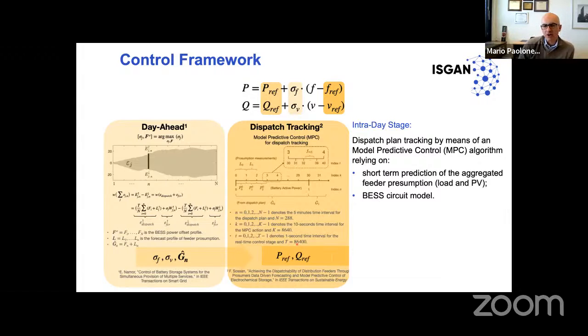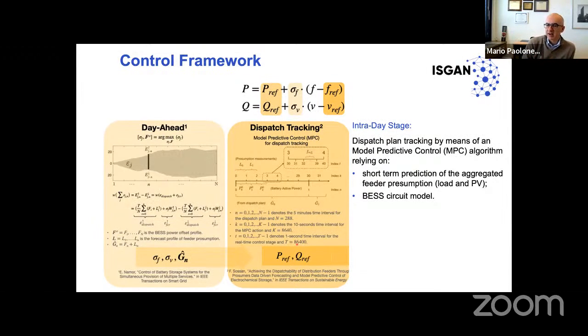This is realized by a model predictive control algorithm, which is acting in this intraday time horizon. As I said, this depends on the granularity of your dispatching plan. It can be 1 hour, 30 minutes, or 15 minutes. In our case, it was 5 minutes. And this MPC is using short-term predictions of the aggregated feeder consumption, so essentially load and photovoltaics. And it's also using the battery circuit model, in our case an equivalent circuit model, to simulate the battery DC voltage, which is then also used for the capability curve computation.